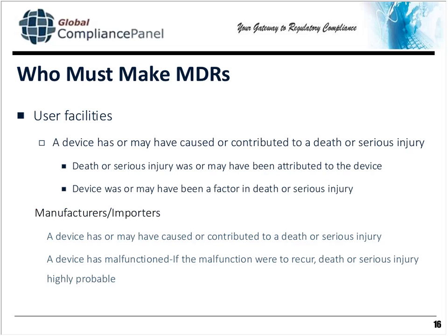Okay. Again, who has to do this? Either user facilities or manufacturers have to make MDRs. User facilities only have to do it if that device may have caused or contributed, or has caused or contributed, to a death or a serious injury. And manufacturers or importers have to do it if that device may have caused or contributed to a death or serious injury, or it has malfunctioned. And if that malfunction were to recur, a death or serious injury is highly probable. So remember, the probability of the malfunction is not an issue at this point. If the malfunction were to recur, a death or serious injury is highly probable. But these are 30-day reports as a rule.